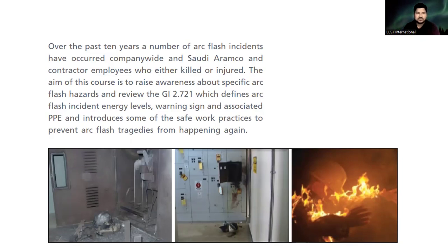Of course, the aim is very straightforward: we have to raise awareness, especially related to arc flash hazards. There is a GI 2.721 general instruction of Aramco, which defines arc flash incident energy levels, warning signs and associated PPE, and introduces some of the safe work practices to prevent arc flash tragedies from happening again. And look at the picture.